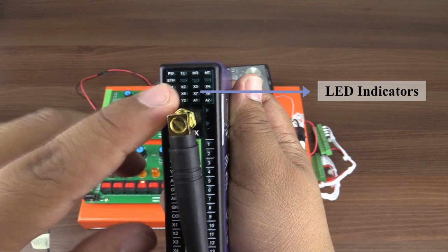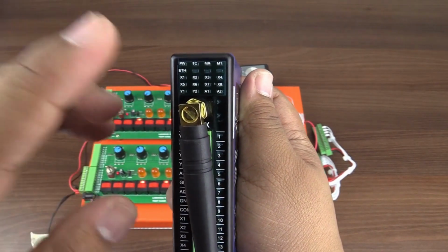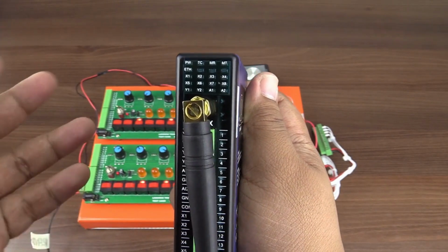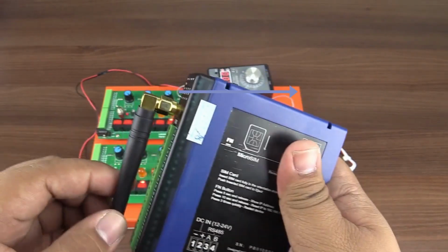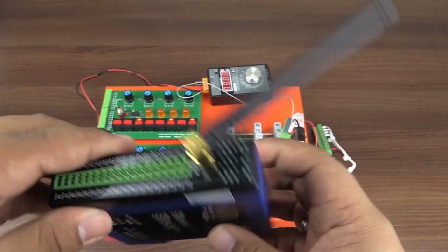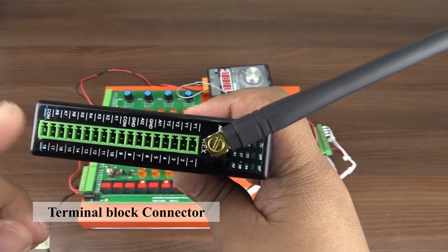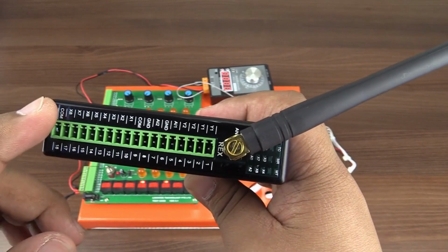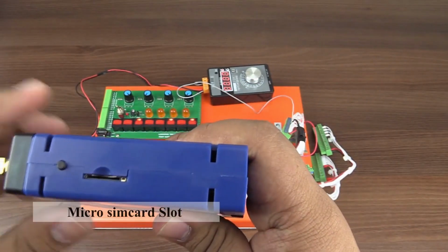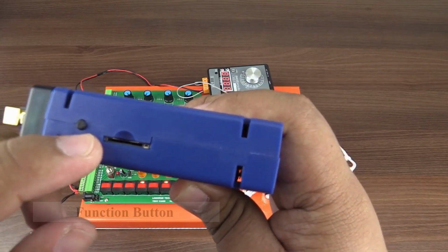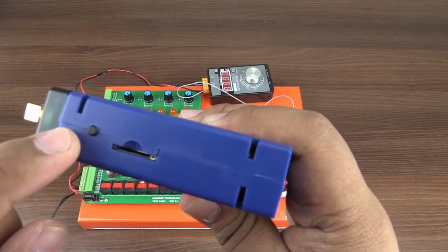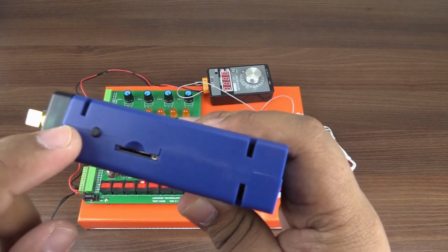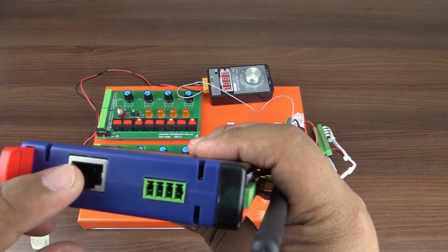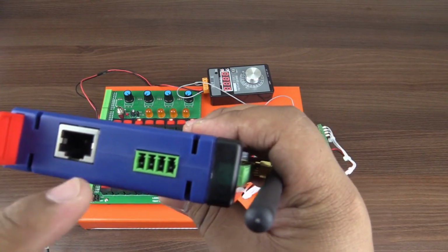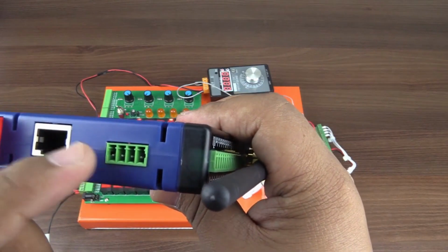At the front side, here are the LED indicators, so you can see the status of the device itself and also the input and output status of every device connected to Rex. It also has an antenna connector, a terminal block connector on which you will connect the devices that you want to monitor. At the top part, there is a SIM card for a micro SIM and a function button that if you press for 5 seconds, it can show the IP of the device. And at the bottom part, there is an Ethernet connector and another terminal block connector for power and Modbus communication.